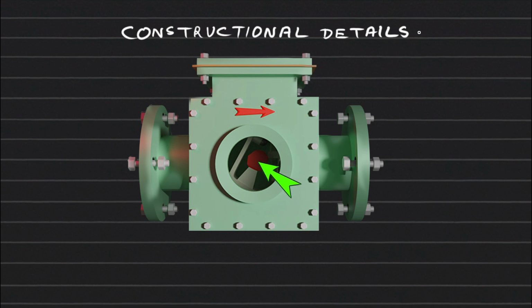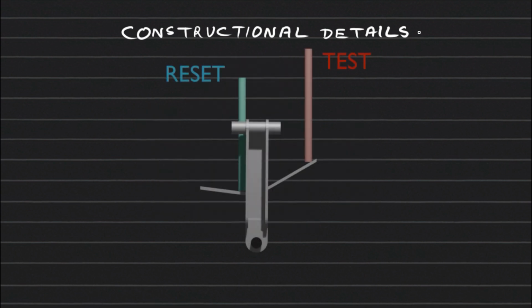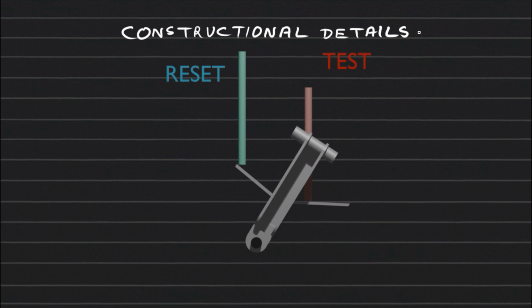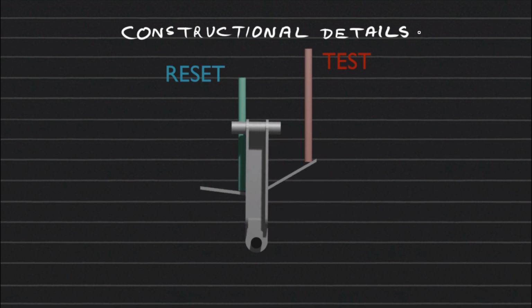When the OSR operates, it indicates a major internal fault in the diverter tank or in the tap changer mechanism. So before resetting the relay, the transformer must be physically inspected by maintenance personnel. Also remember, the OSR cannot be reset remotely. It has a mechanical reset system and must be manually reset at the site. Although we have not shown the test and reset lever here, in different animations we can show. When we push the red lever, the relay manually operates, so it is a test lever. The blue lever is pushed to make the flap return to its original position, so it is a reset lever. Once the OSR has operated, the transformer must not be re-energized until it is physically reset.